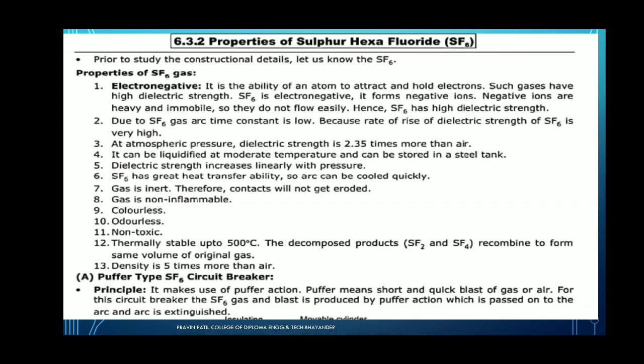Electronegative means it is the ability of the atoms to attract and hold electrons. Such gases have high dielectric strength. SF6 is electronegative. It forms negative ions. Negative ions are heavy and immobile, so they do not flow easily because of the heavy weight, and hence SF6 gas has high dielectric strength.